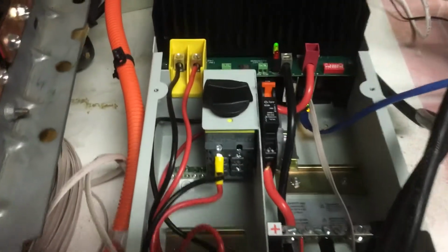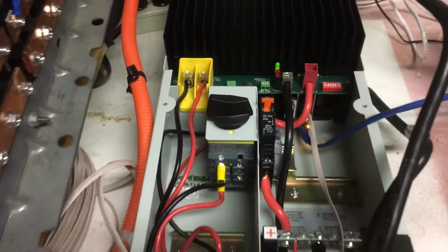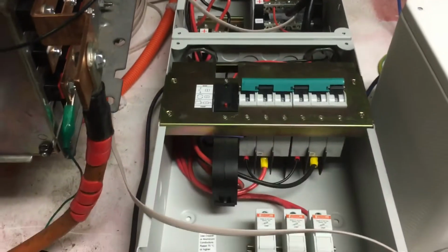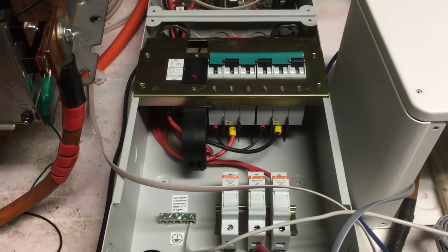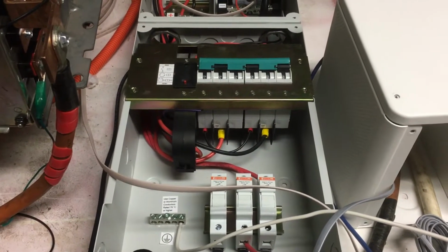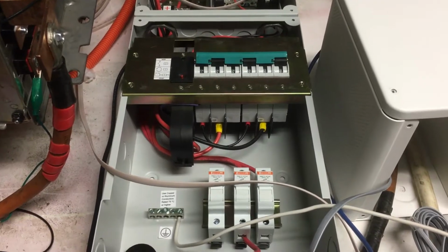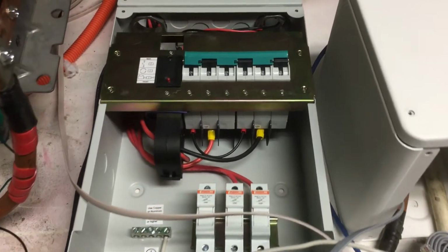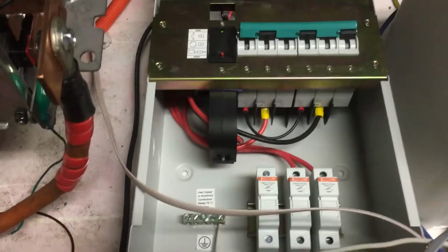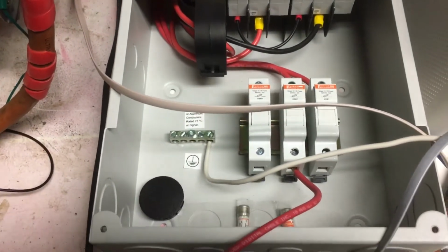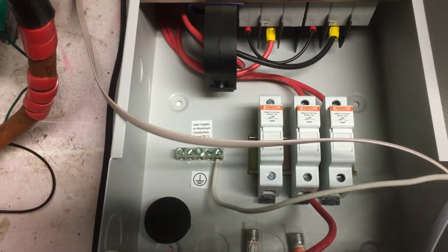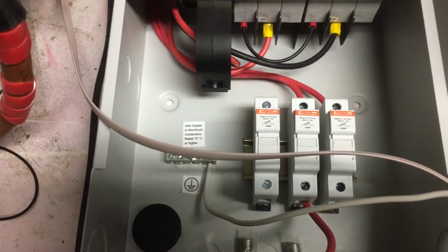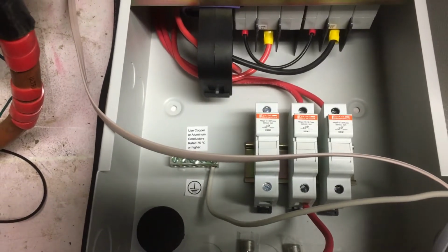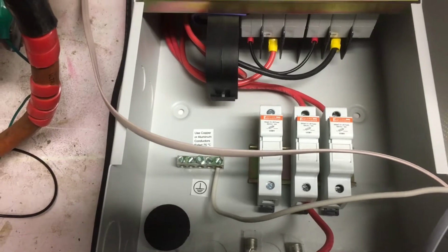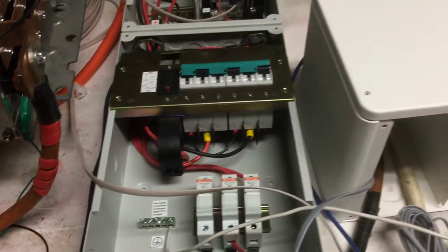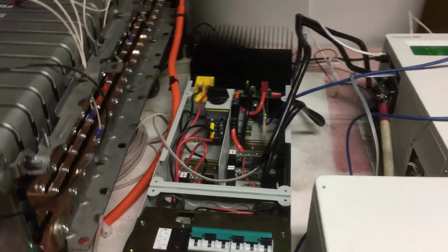It also has the little breaker next to it there as the battery disconnect built in. And then this one has the ground fault protection box as well. I figured since we're putting 300 volt solar strings on the roof, it would be a good idea to have that. There's enough room in these boxes that I've added some DIN rail fuse holders at the bottom. So that's where the fuses for each string of the solar will go, and another fuse for the input from the Prius. That's how we'll normally be charging.